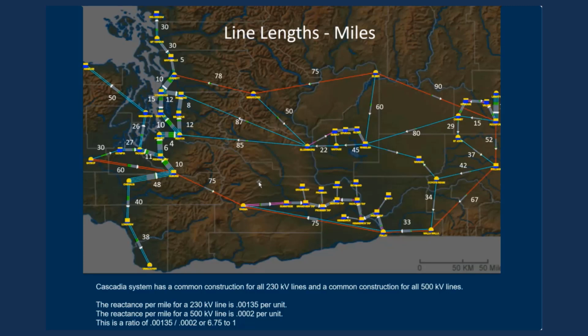The Cascadia system has a common construction for all 230 kV lines and 500 kV lines. The reactance per mile for a 230 kV line is 0.00135 per unit. The reactance per mile for a 500 kV line is 0.0002 per unit. If we take the ratio, then the reactance of the 230 is 6.75 times the reactance of the 500 kV for each mile of length.